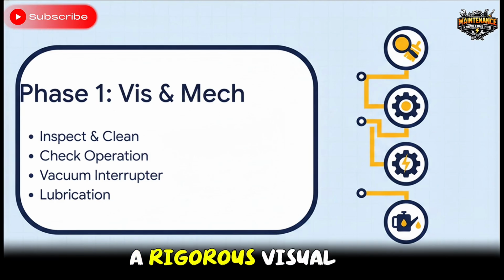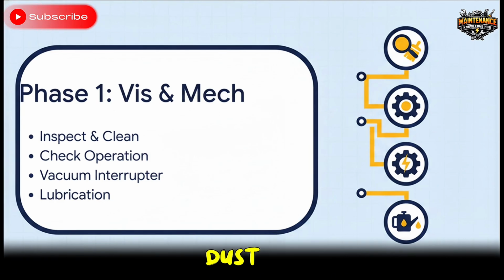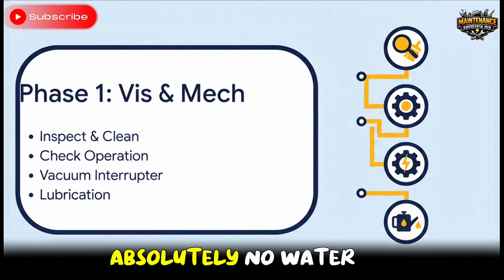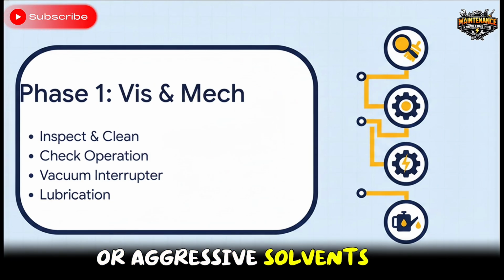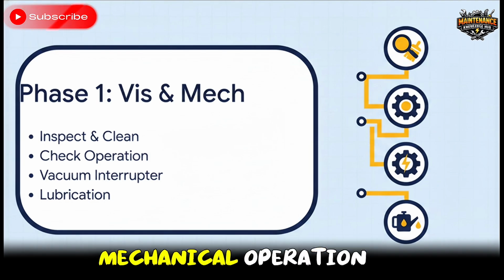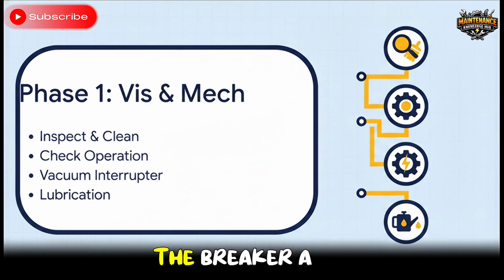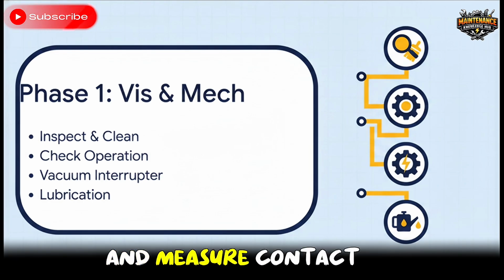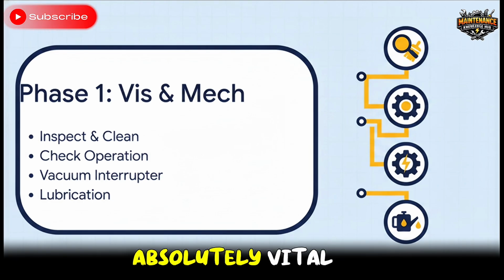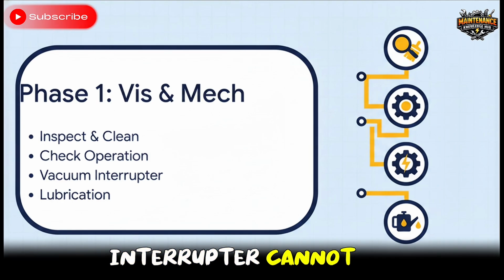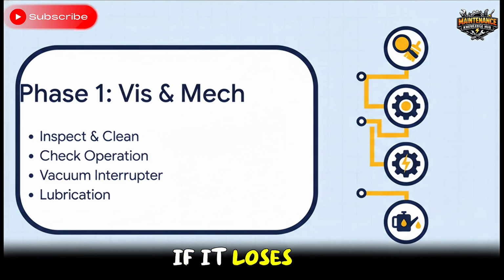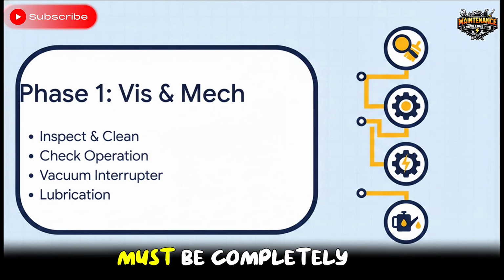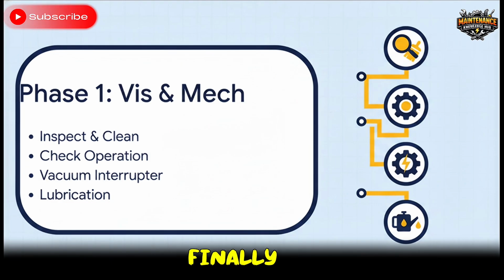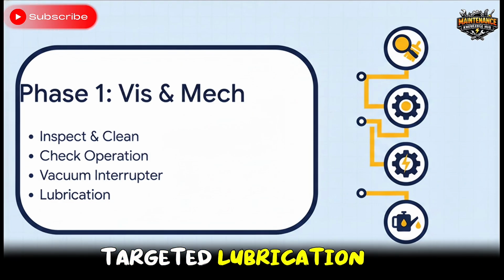You start with a rigorous visual inspection, looking for any dust, cracks, or rust, followed by a dry cleaning. And remember, absolutely no water or aggressive solvents here. Next, check the mechanical operation by manually operating the breaker a few times. Then you inspect the vacuum interrupter itself and measure contact wear. This is absolutely vital because a vacuum interrupter cannot generally be repaired. If it loses its vacuum integrity, it's done. It must be completely replaced. Finally, we finish phase 1 with some targeted lubrication.